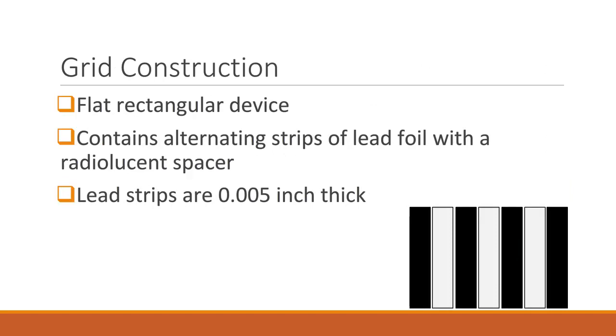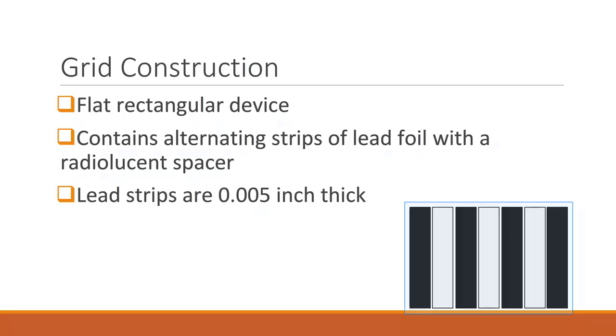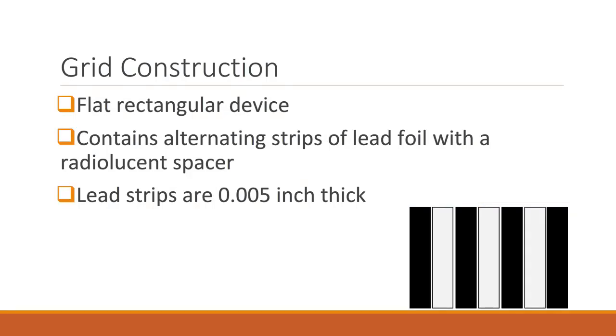A grid is a flat rectangular device that contains thin lead foil strips and radiolucent spacers. The lead strips are 0.005 inches thick, or 5 thousandths of an inch thick. The lead strips and spacers are alternated. Some grids are located inside the table or upright Bucky where you don't see them, while other grids can be attached to a specific size image receptor.